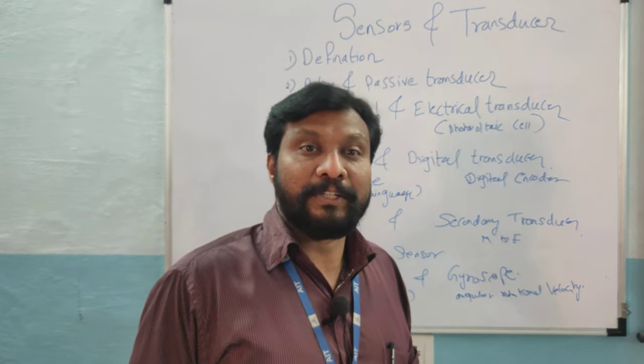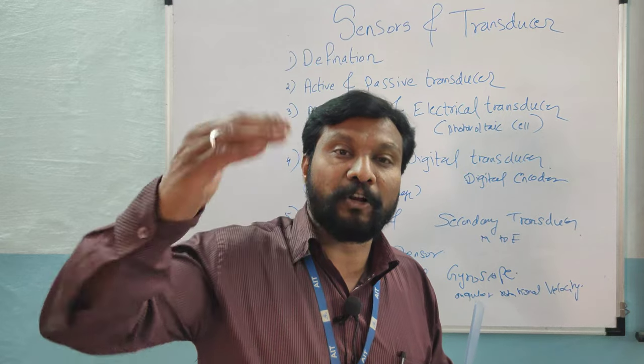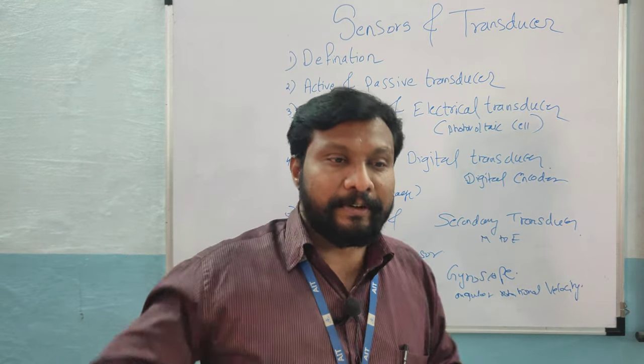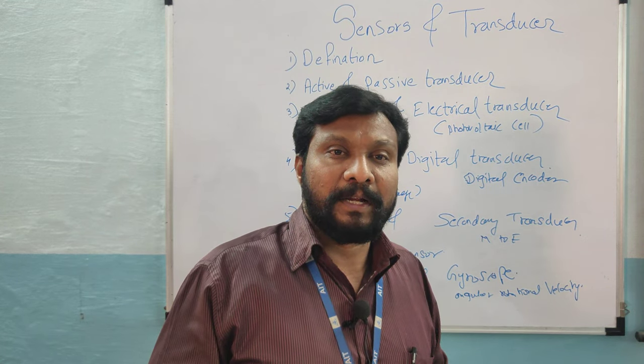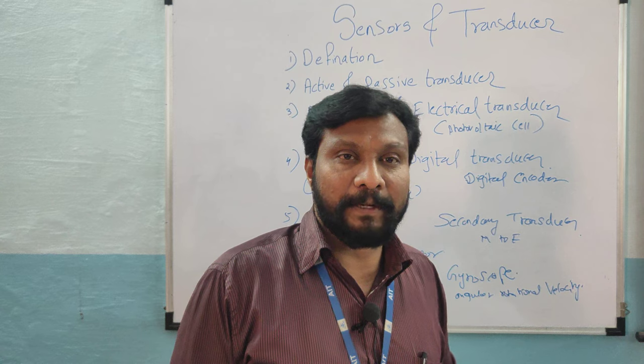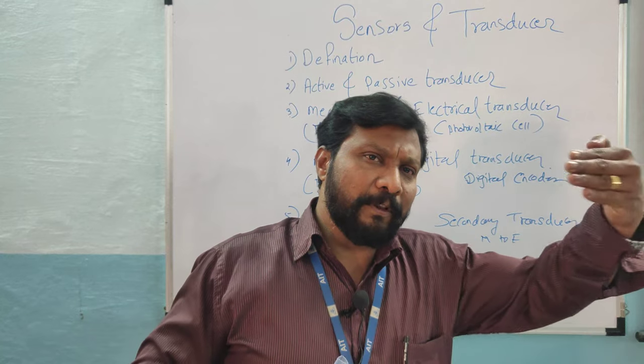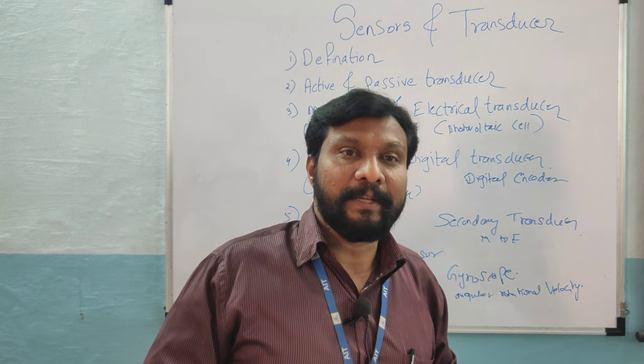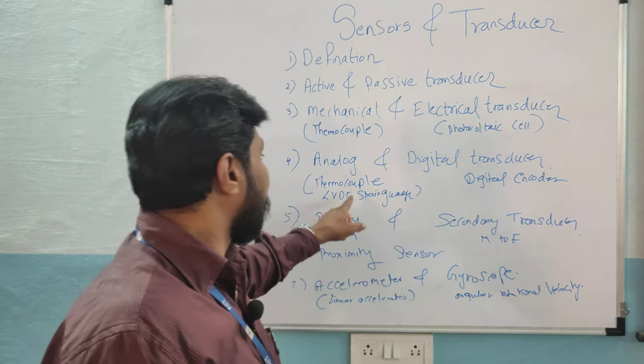Analog transducers generate an analog output corresponding to the physical quantity being measured. Examples include the thermocouple, LVDT, and strain gauge. LVDT — Linear Variable Displacement Transducer — has an iron core placed between primary and secondary windings. Depending upon the movement or displacement of the iron core, a voltage is generated, allowing us to measure the displacement of an object.